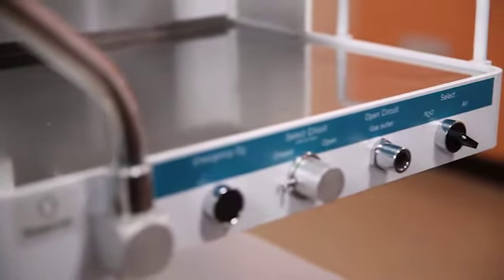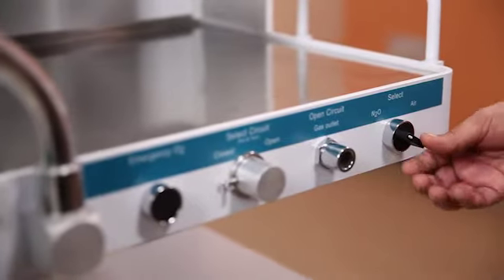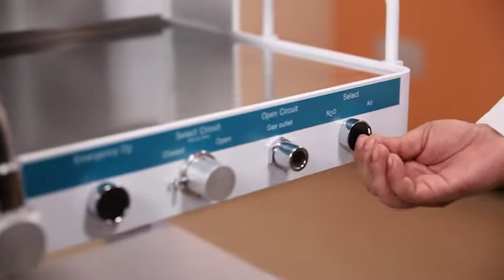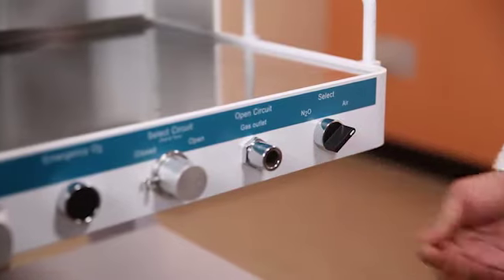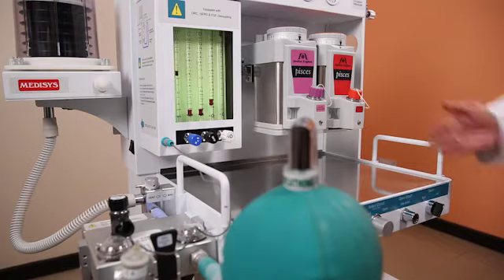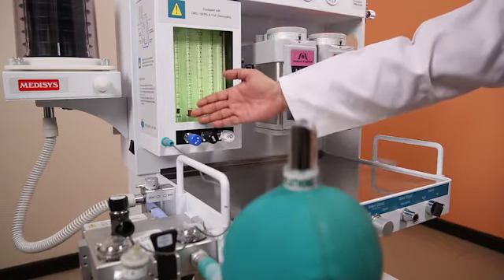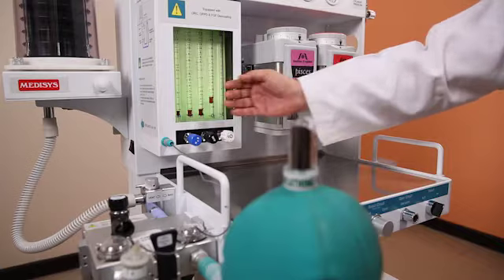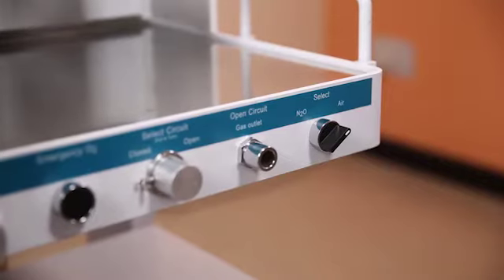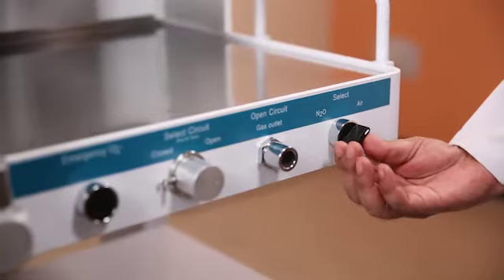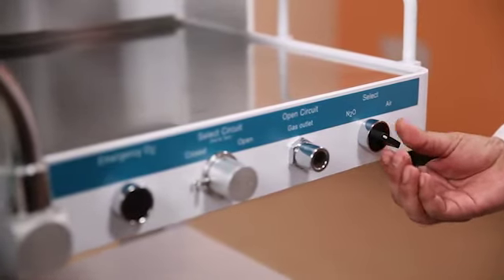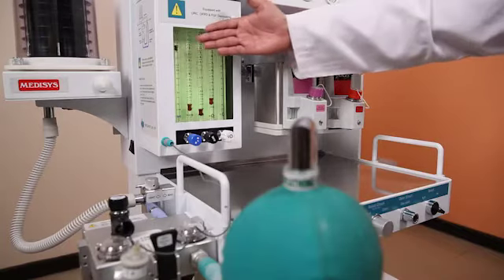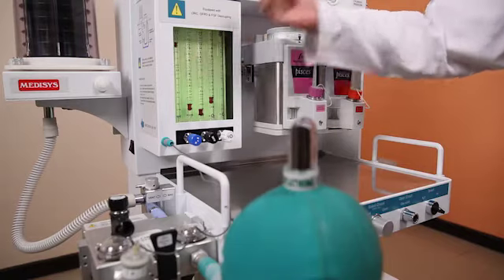Another very interesting safety feature in this machine is the air nitrous oxide lock. By this we mean that if nitrous oxide is running, air cannot be put in, and when you want to use air, nitrous oxide will not run. By simply flicking a switch, nitrous oxide and air will never run simultaneously. This is a big safety factor.